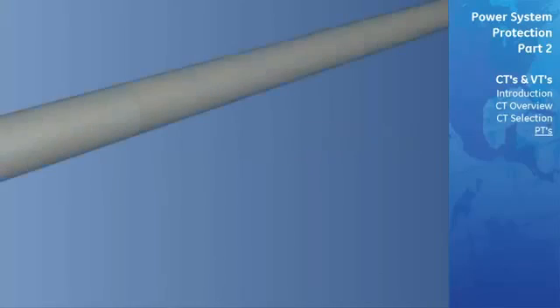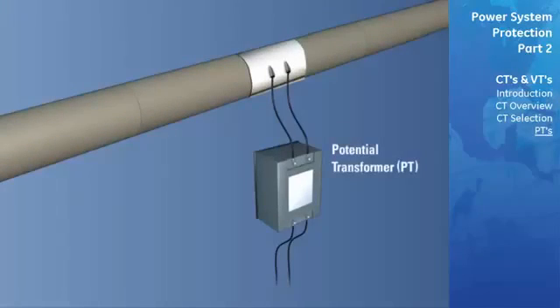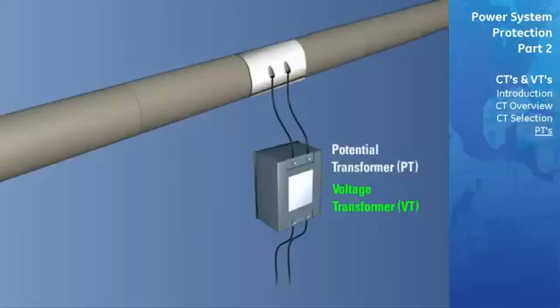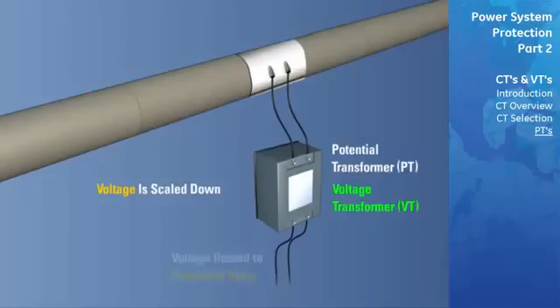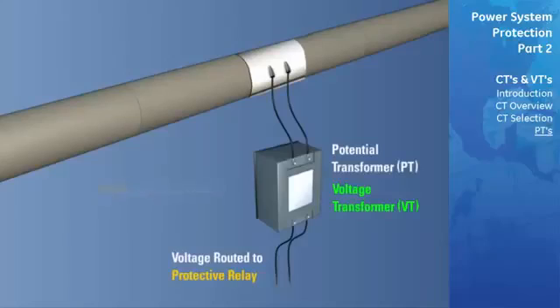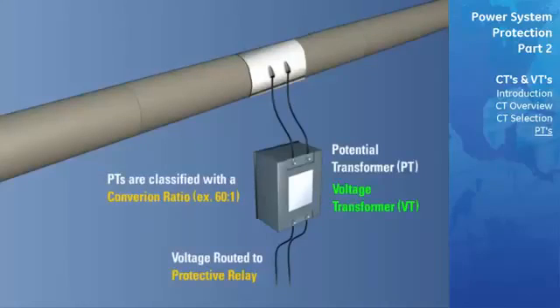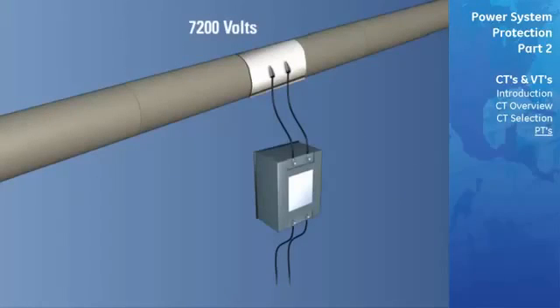The next type of transformer we will cover is the potential transformer, symbolized as PT, or sometimes known as voltage transformers symbolized as VT. Similar to current transformers, potential transformers scale down the voltage passed through them, as opposed to current. The scaled-down voltage is then routed to a protective relay for measurement. A PT is classified with a conversion ratio indicating the amount the primary voltage is scaled down. For example, 60 to 1 scales the primary voltage down to 120 volts.